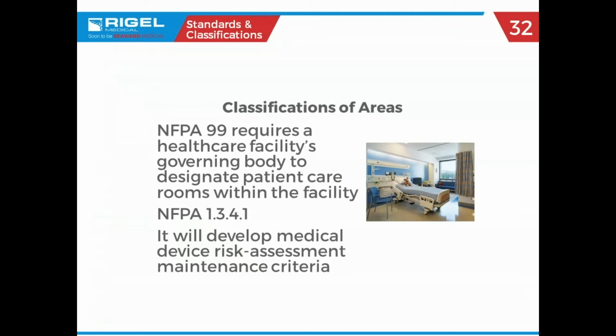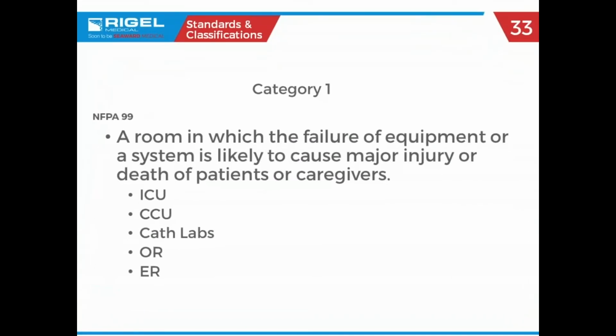So designate patient care rooms within the facility, part of NFPA 99, 1.3.4.1, and get right to it. Category 1, most stringent. Makes sense when you look at this stuff, right? ICUs, CCUs, cath labs, OR, ER. Because these are typically, especially OR, could be ER as well, this is when the body is probably at most risk, right? I mean, there's something going on that's bad already. Got fluids, you can have all kinds of things going on. So the risk of electrical safety, risk of electrical shock is higher than anywhere else in the hospital in these areas.